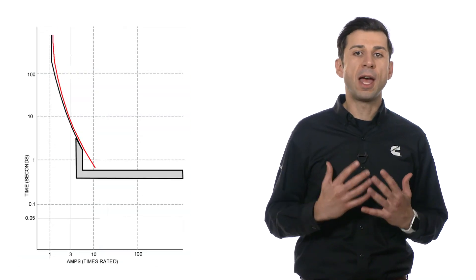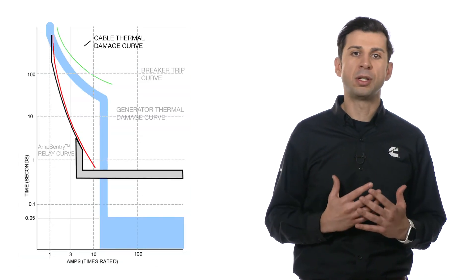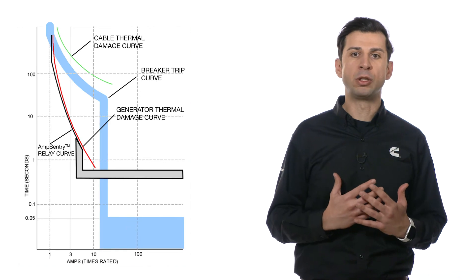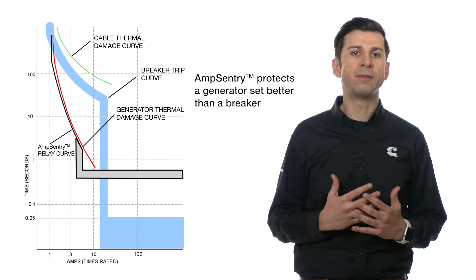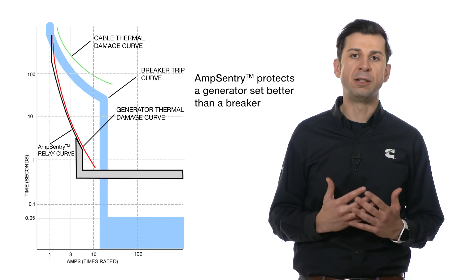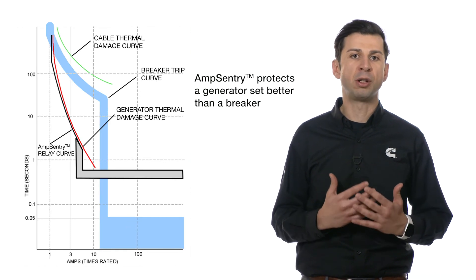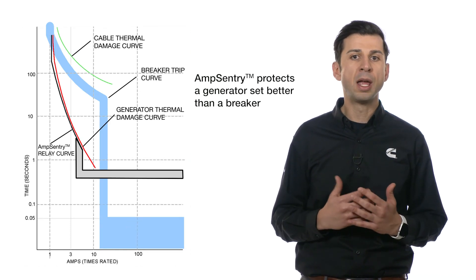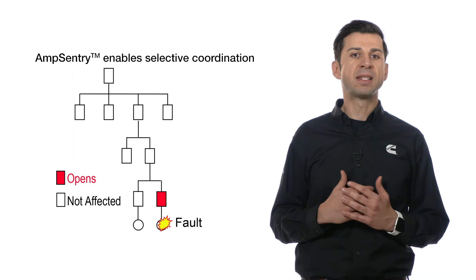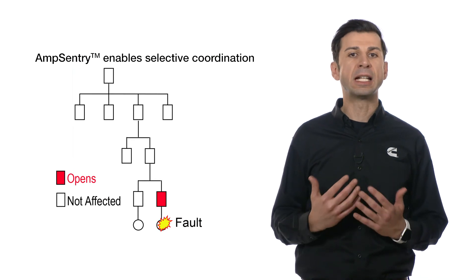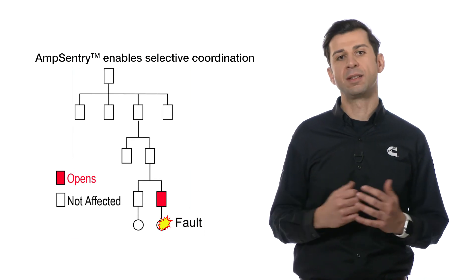Therefore, Amp Sentry protection in power command controls effectively eliminates the need for a main generator set breaker and enables systems to be selectively coordinated. The power command control also has a unique protection element called maintenance mode.